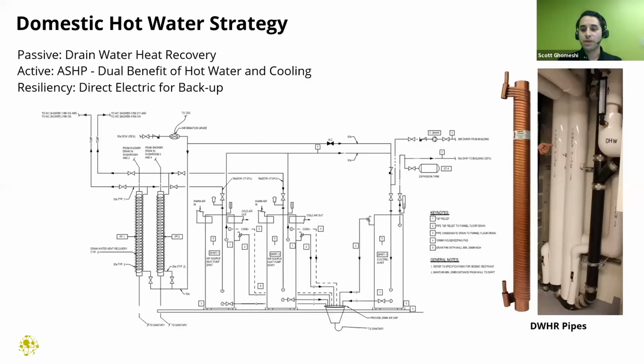Here, what we started with was utilizing drain water heat recovery wherever we could. Very early in design, we tried to locate the showers in a location where it could facilitate the drain water being collected in one place, so that we could recover that waste heat and use it to temper the cold water that would then feed up to the showers or over into a couple of tanks.